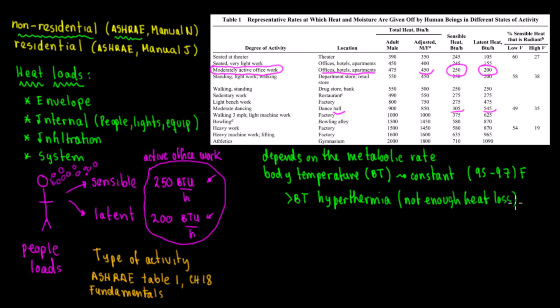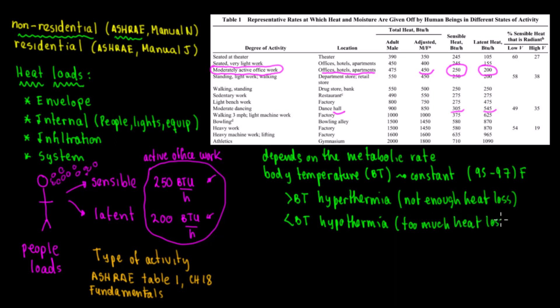As a contractor or engineer, this extra information improves your assumptions. You can say: the heat load is 250 BTU/hr based on ASHRAE Fundamentals Table 1 because we're maintaining constant body temperature — otherwise we'd have hyperthermia or, on the opposite end, hypothermia, which is too much heat loss causing the body to get cold.